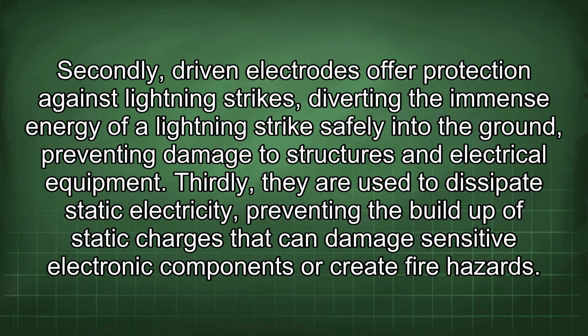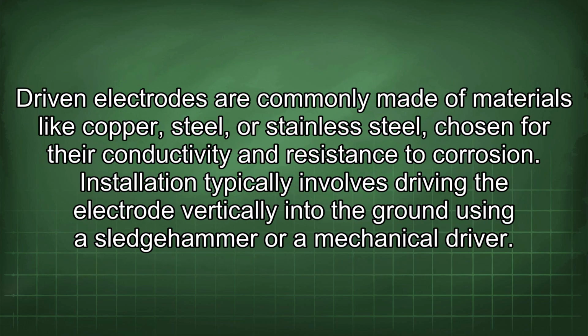Thirdly, they are used to dissipate static electricity, preventing the buildup of static charges that can damage sensitive electronic components or create fire hazards. Driven electrodes are commonly made of materials like copper, steel, or stainless steel, chosen for their conductivity and resistance to corrosion. Installation typically involves driving the electrode vertically into the ground using a sledgehammer or a mechanical driver.